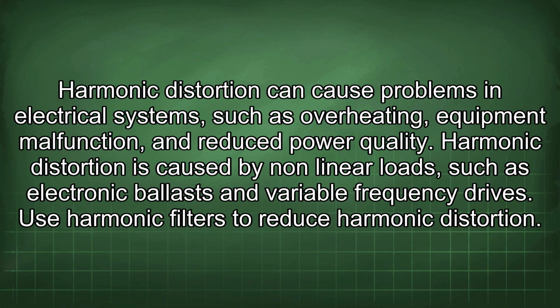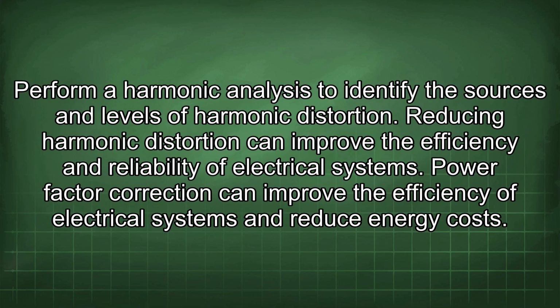Harmonic distortion can cause problems in electrical systems, such as overheating, equipment malfunction, and reduced power quality. Harmonic distortion is caused by nonlinear loads, such as electronic ballasts and variable frequency drives. Use harmonic filters to reduce harmonic distortion. Perform a harmonic analysis to identify the sources and levels of harmonic distortion. Reducing harmonic distortion can improve the efficiency and reliability of electrical systems.